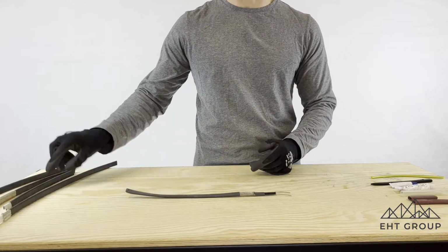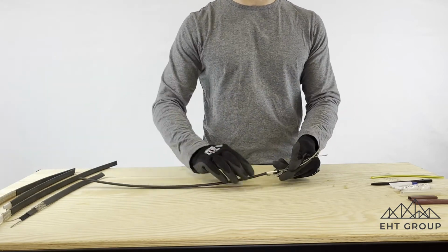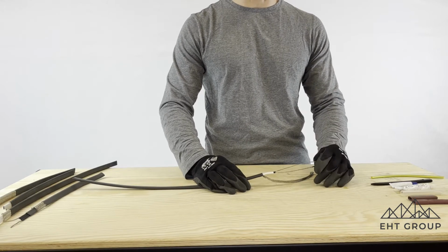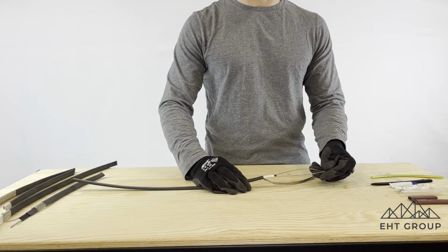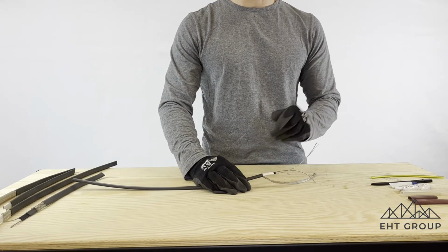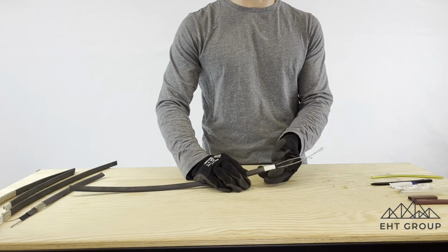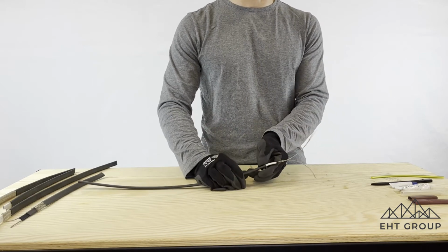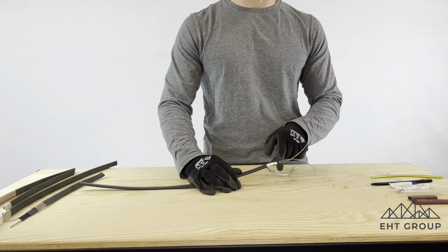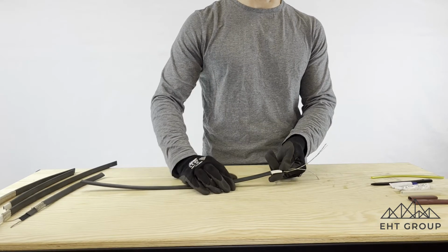So for a power termination, we're typically seeing a power termination done something like this. There's going to be some variations based on manufacturers and power termination points, but this will give you a good idea. So we'll see our outer sheath has been cut back. There is the braid, which has been taken off and is coiled up, and we're taking some really good care, making sure that we don't see any random strays of braid that's coming close to our bus bars or semiconductor.